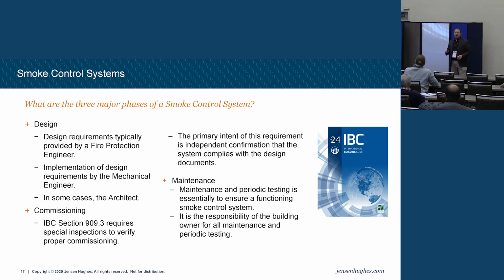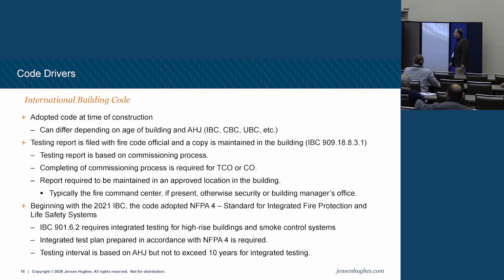But then if you say, okay, now I need you to shut that off, go into full exhaust mode, no supply, they're like, we didn't design it for that. Well, that's because you weren't thinking about the life safety piece. And when we start talking maintenance, they can make changes to balance a system that ruin a smoke control system. So all three are pretty critical pieces.